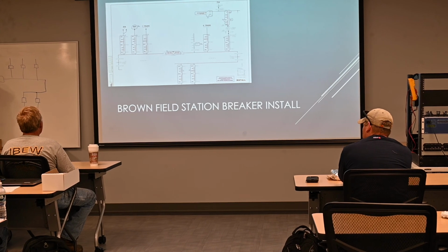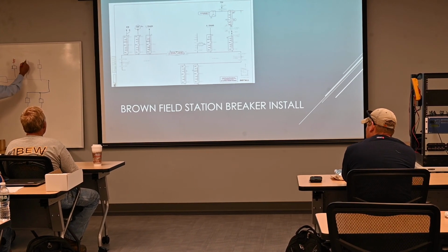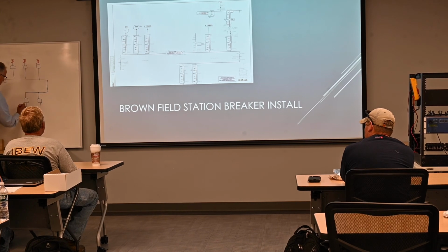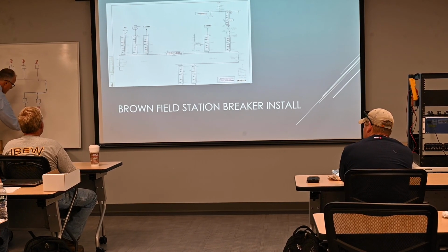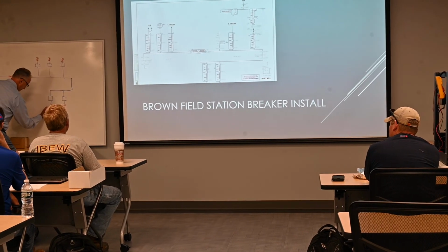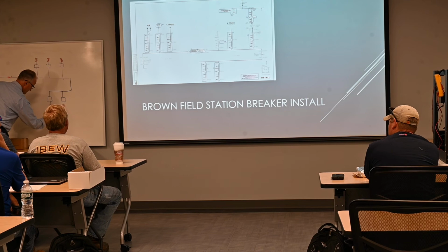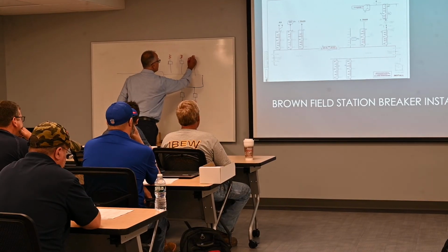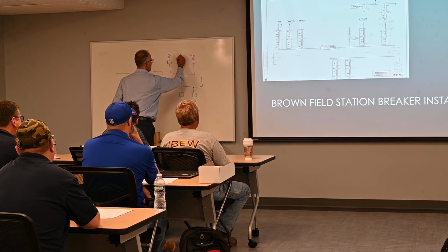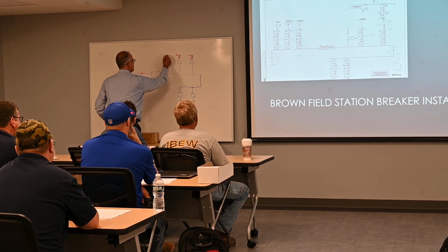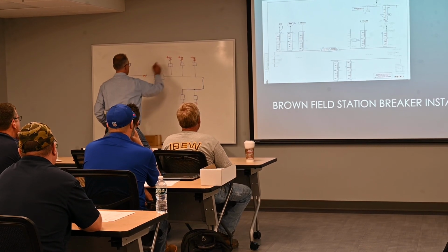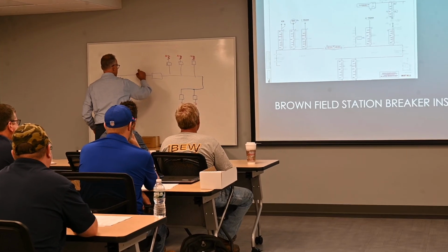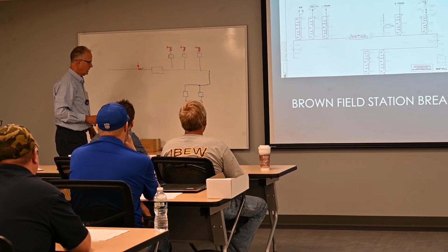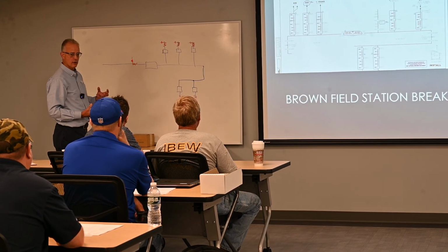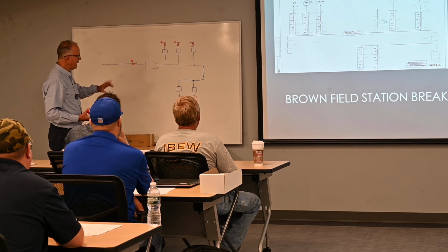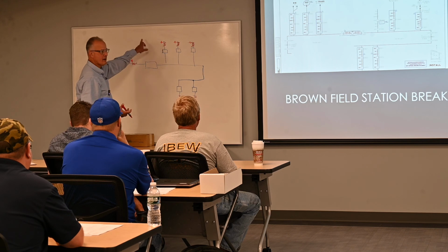All right, so there's a CT here, here, here, here, and here. And I'm going to put a polarity mark on each CT that is away from the zone of protection. That's typically how you're going to always see the CT configurations for a bus differential. You may have the polarity mark on the other side, but the wire is going to come off the other side, all right.